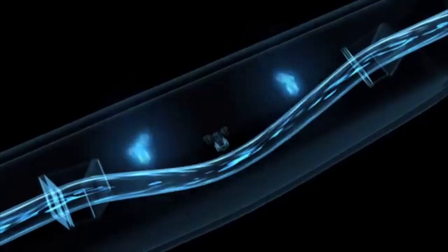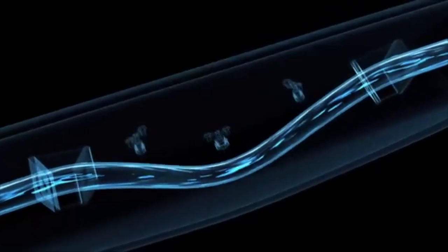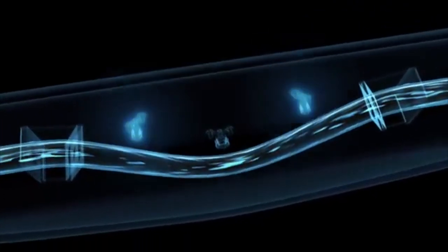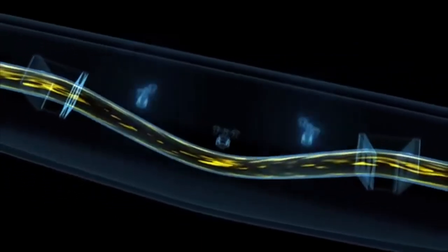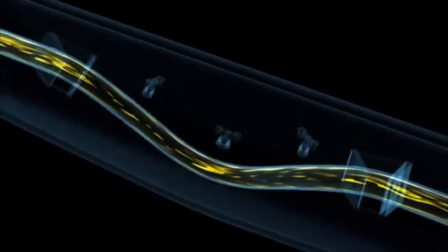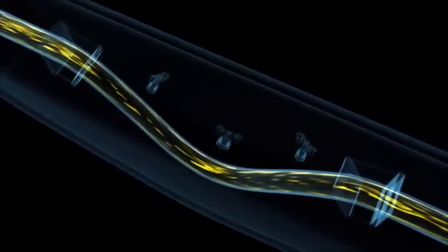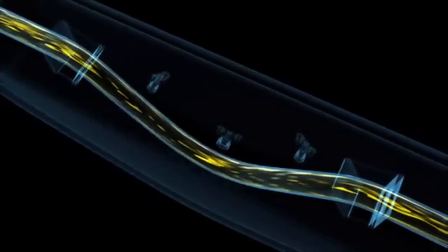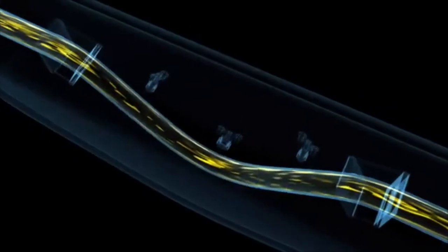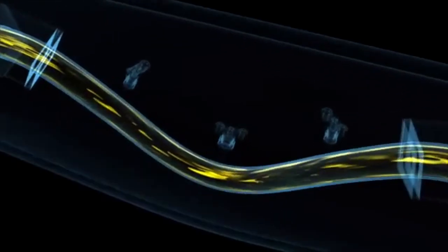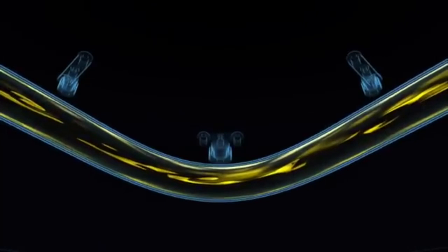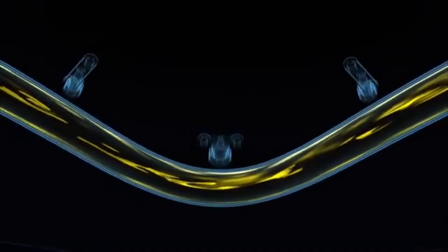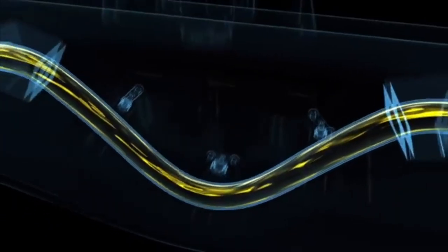From this animation, it is clear that a tube filled with water oscillates more frequently than a tube filled with honey, for example, which has higher density. Thus, the oscillating frequency is a direct measure of fluid density. Both density and flow are measured simultaneously but independently via tube oscillation.